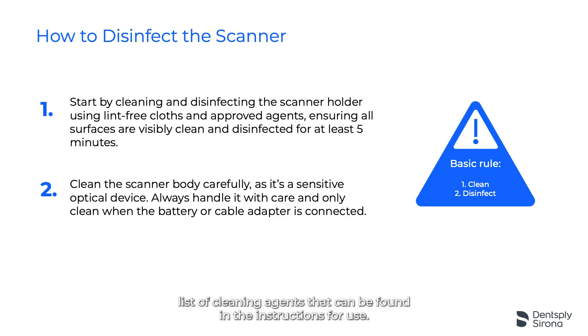Proper disinfection is key to maintaining patient safety. Start by cleaning and disinfecting the scanner holder using a lint-free cloth and approved agents, ensuring all surfaces are visibly clean and disinfected for at least 5 minutes. Please refer to the approved list of cleaning agents that can be found in the instructions for use.